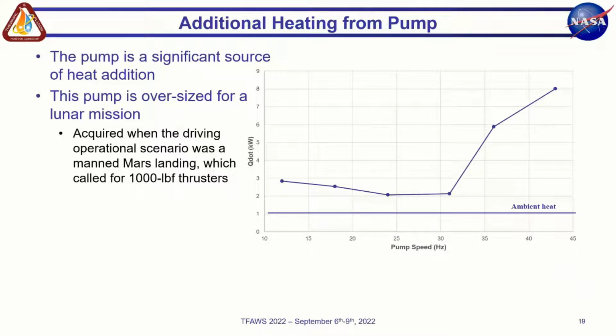We showed the ambient heat here, and then the heat rate from different speeds as the pump's running, to get an idea of what the heat load is going to be from simply running this pump. And we especially noted that as the pump starts running at higher speeds, we start getting quite significant heat loads compared to just the ambient heat. One thing to note, the pump that we had on hand in the lab was oversized compared to the reference mission that we had built our test series for. When we acquired the pump, we were designing this concept towards a manned Mars landing, which called for much larger flow rates. So that's one of the reasons our heat load gets so high here.